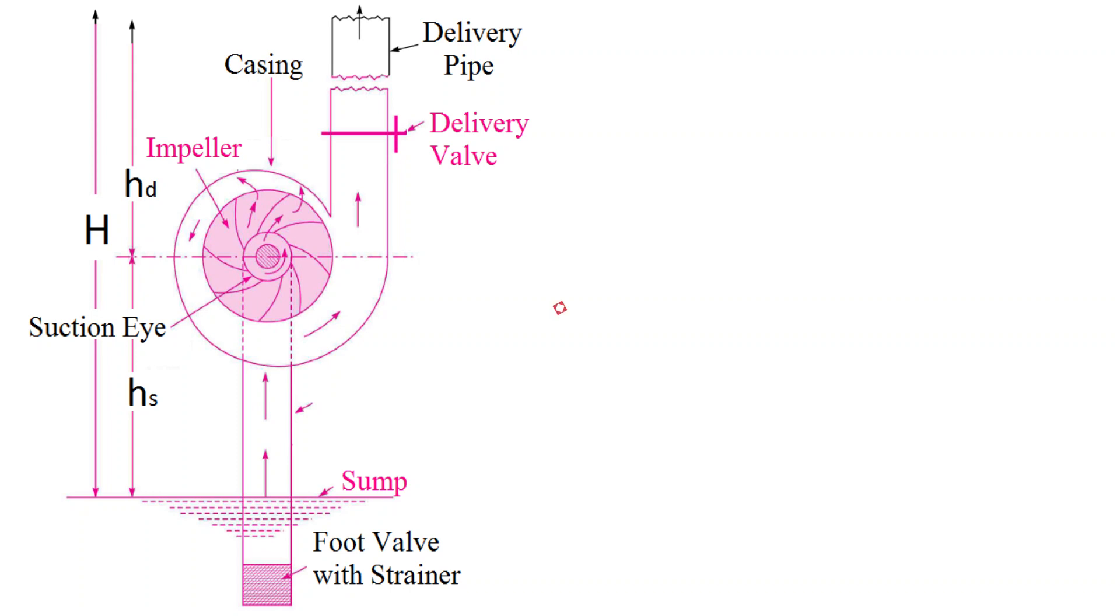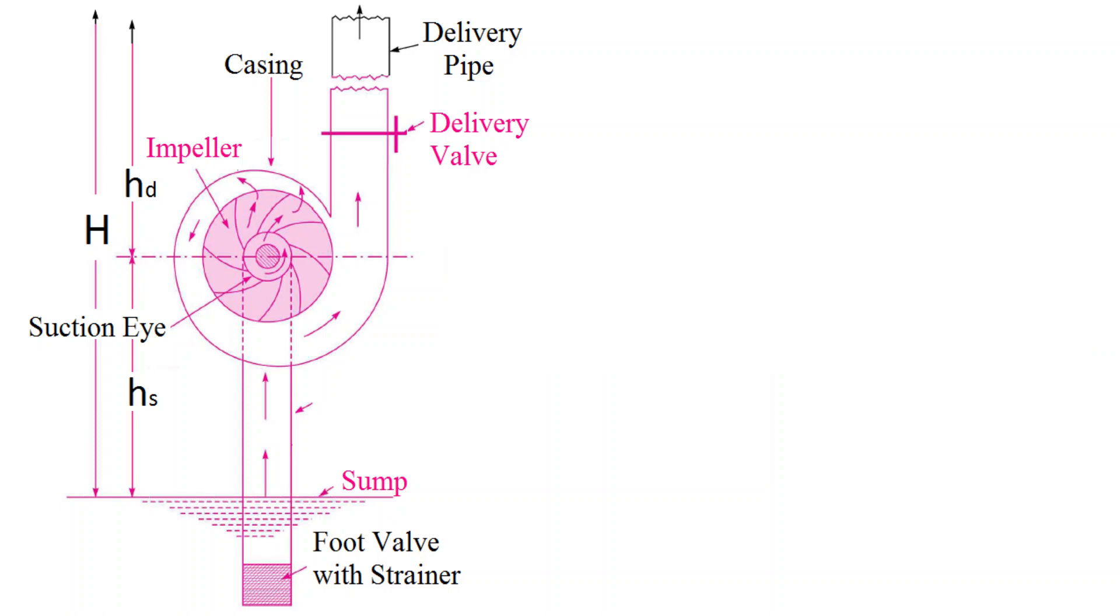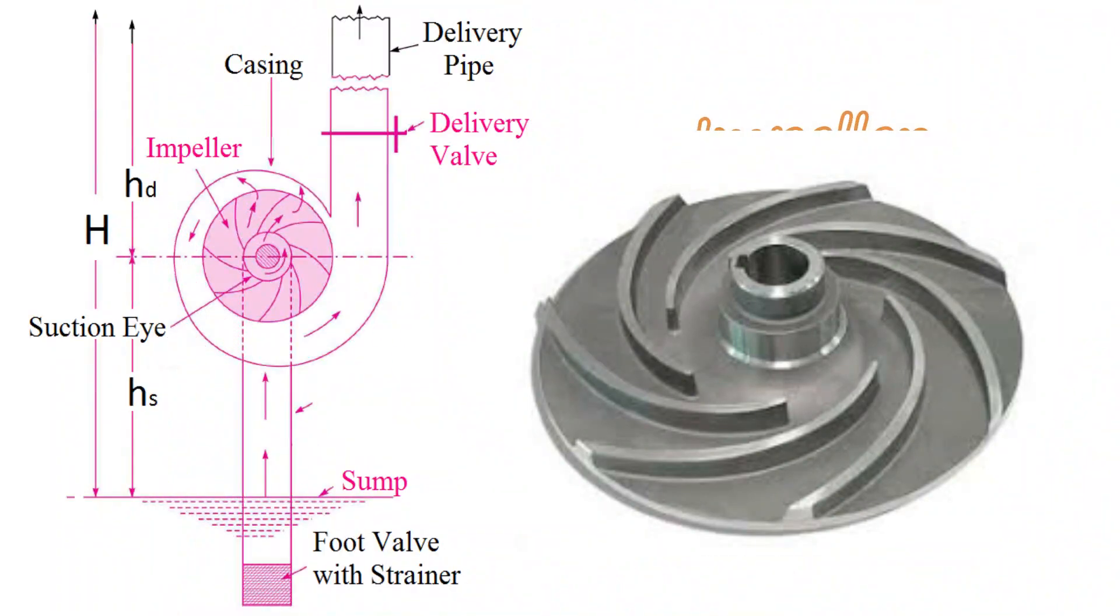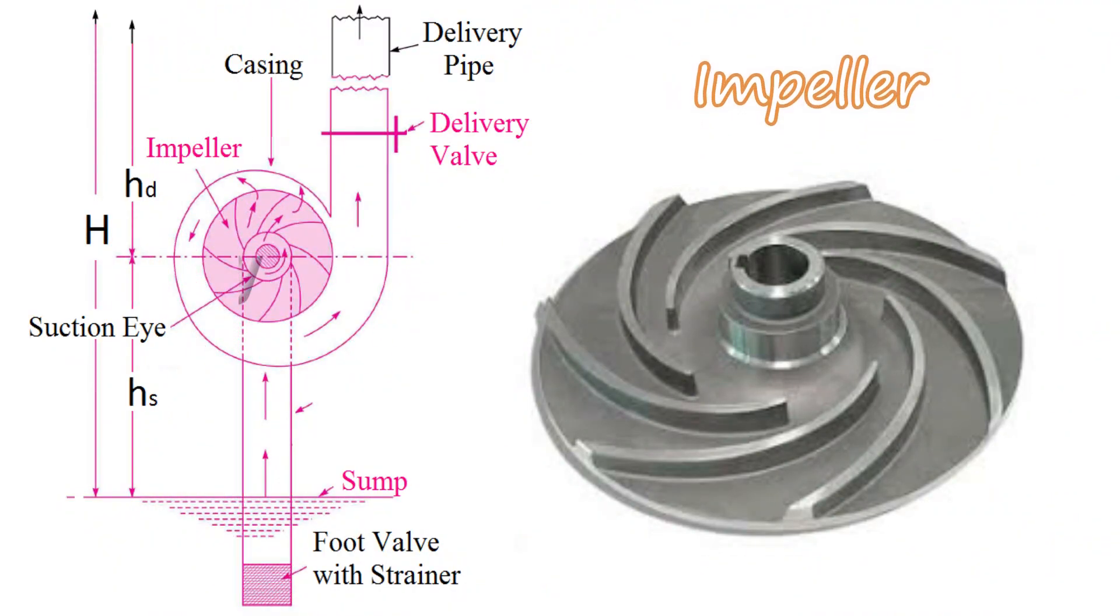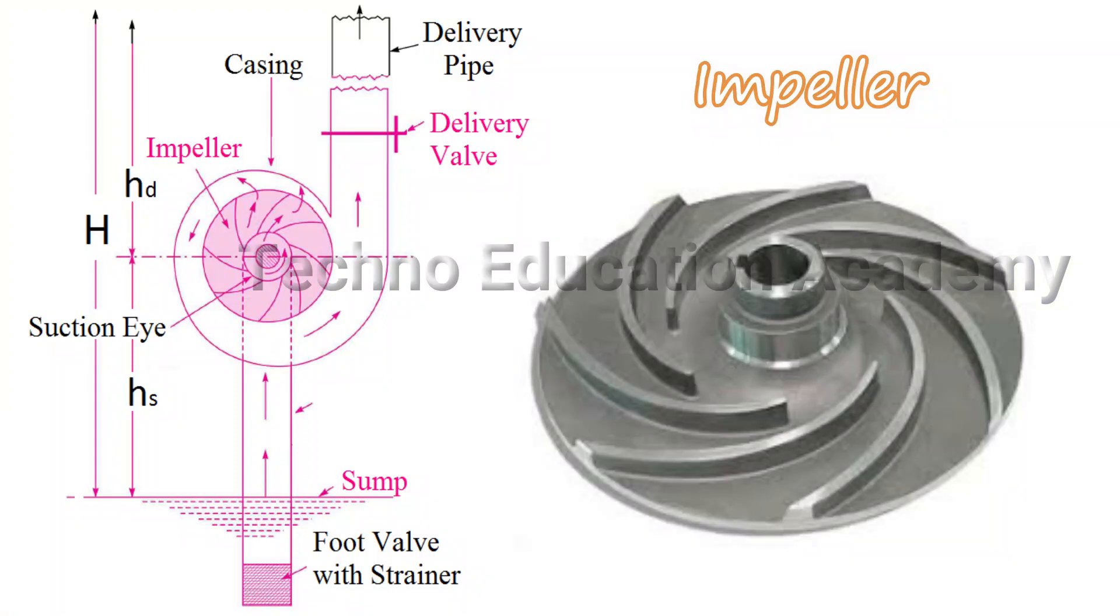Now we will discuss the main parts of centrifugal pump. Then after I will explain working principle of centrifugal pump. So the first component of centrifugal pump is impeller. The rotating part of centrifugal pump is called impeller. It consists of series of backward curved vanes. The impeller is mounted on shaft which is connected to the shaft of an electric motor or internal combustion engine. In generally in agriculture application, the pump is driven by IC engine. The function of the impeller is to convert kinetic energy into pressure energy. How can it convert kinetic energy of liquid into pressure energy that I will explain to you during explanation of working principle of centrifugal pump.